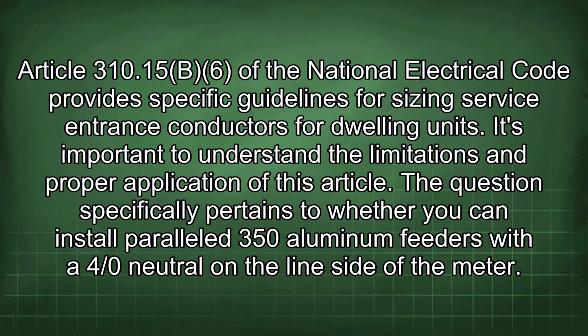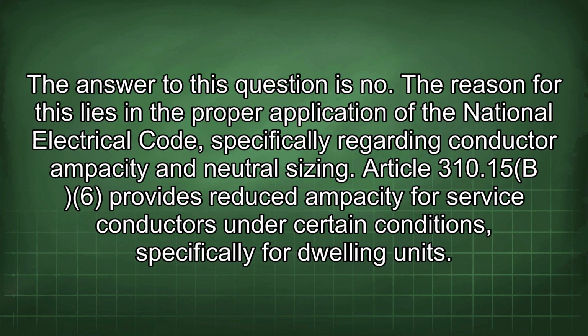Article 310.15(B)(6) of the National Electrical Code provides specific guidelines for sizing service entrance conductors for dwelling units. It's important to understand the limitations and proper application of this article. The question specifically pertains to whether you can install parallel 350 aluminum feeders with a 4/0 neutral on the line side of the meter. The answer to this question is no.